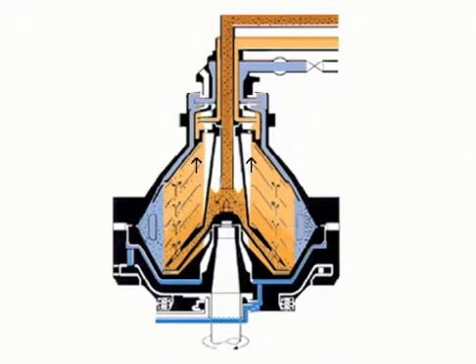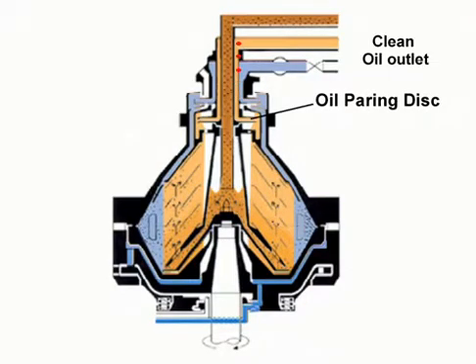When the cleaned oil leaves the disk stack, it rises upwards and flows over the level ring and enters the oil-paring chamber. The oil is pumped by the oil-paring disk and leaves the bowl through the outlet.